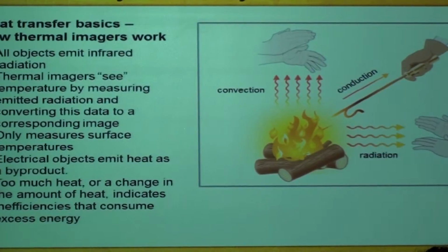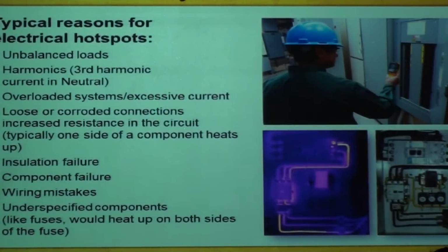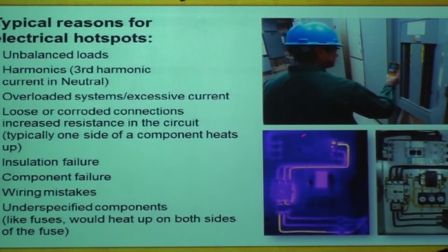So if you're looking at cables, motor terminations and so forth, you need to get those covers open, because if it's not open, you're not going to see the condition of the panels inside. Electrical objects emit heat as a byproduct. Too much heat or a change in the amount of heat indicates an inefficiency. And that's what we want to measure. So, measurement theory, the electrical heat, or what we call the delta T, the difference in temperatures, typical reasons for electrical hotspots. Harmonics is a very good indication, because harmonics is extra energy that's always added, and extra energy means extra I squared R, which is extra heat. And that's what you see on cabling.